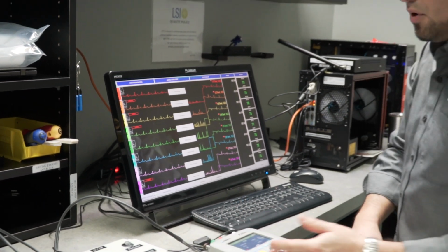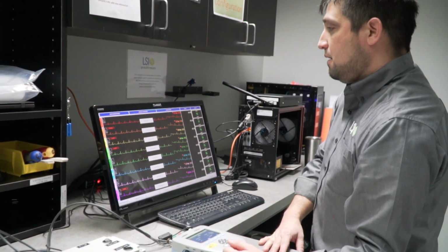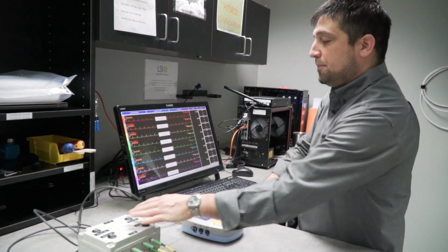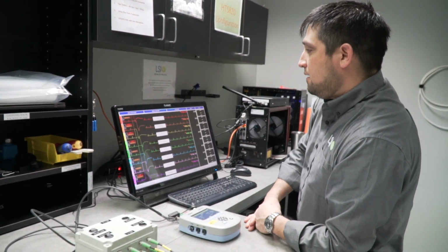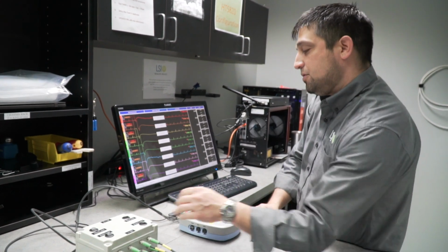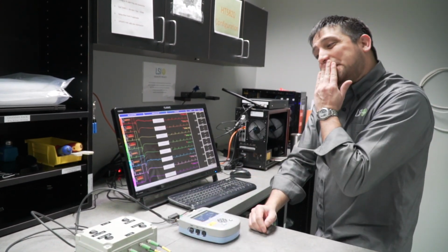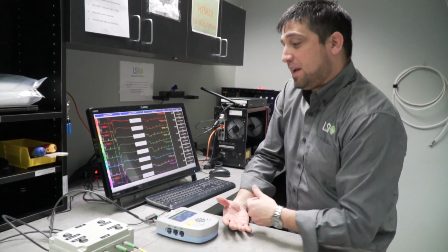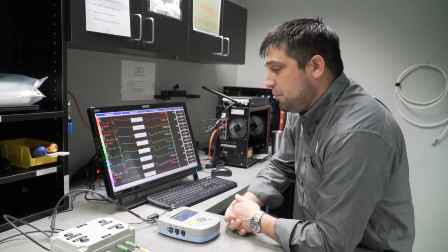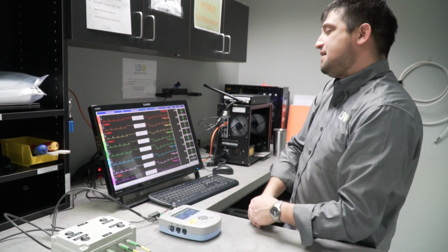We could do the same for the brown. We notice the MCL fault, and then we disconnect the red lead and get lead fault 2. This was not originally in the scope of the project. This was added as we began our design because it speeds up our testing process.